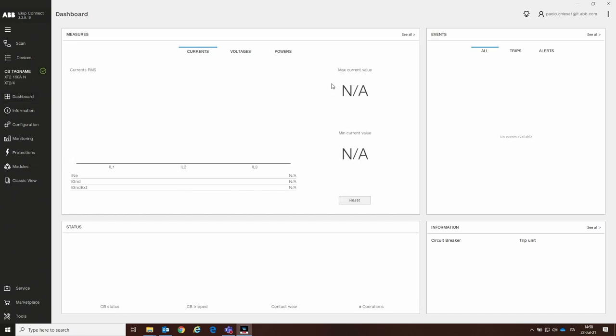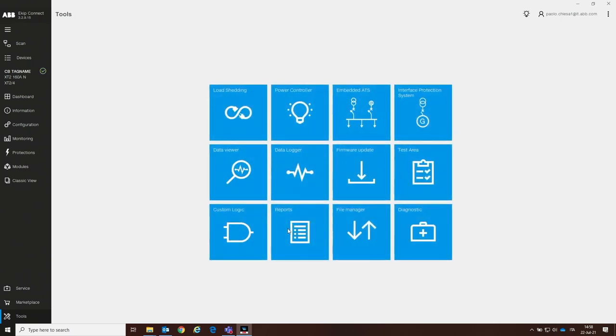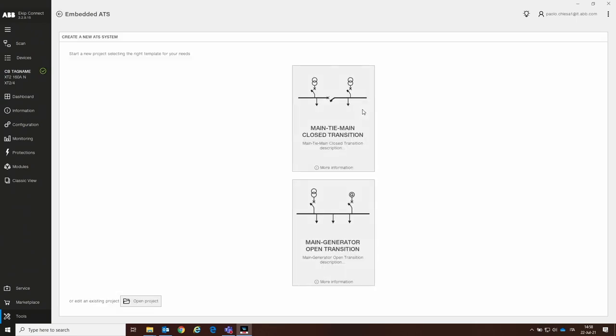Now we need to install the automatic transfer switch main-generator. To do that, we click on the Tools button, where we can find all the tools that we can install on our trip unit. In this case, we are going to click on the embedded ATS functionality. We have two possibilities: the main-tie-main closed transition, or the one related to this video, which is the main-generator open transition.